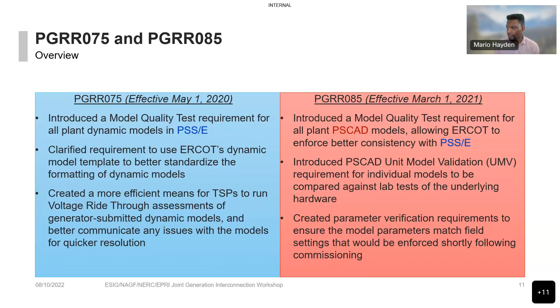85 built upon the spirit of 75, in that it applied those same criteria to PSCAD models. As mentioned earlier, it introduced the unit model validation, which is on an individual basis, comparing the actual inverter or turbine hardware to the actual model that's being supplied. And then finally, the parameter verification, which is for more of an operational time frame, to make sure that the models being supplied match what is actually in the field.